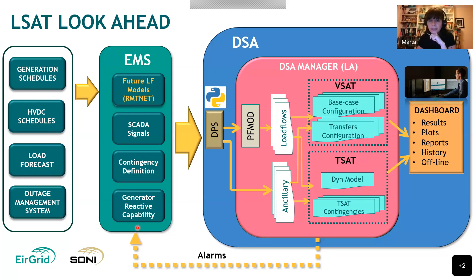So this is real-time functionality. Look ahead is very similar, but rather than starting in EMS from the state estimator solution, we have a different application called RMTNet that generates a series of load flow solutions, starting from data from an external system, from the market and from the outage management system. So we input the generation schedules, the HVDC schedules, the load forecast, and the plan outages. All of that is combined by this application, RMTNet, and it generates a series of load flow cases in PSS raw format version 30. All of that, again, is transferred into the DSA environment, and the process is exactly the same as in real time. We get our results in the dashboard, and we close the loop with the capability of sending alarms back into EMS.